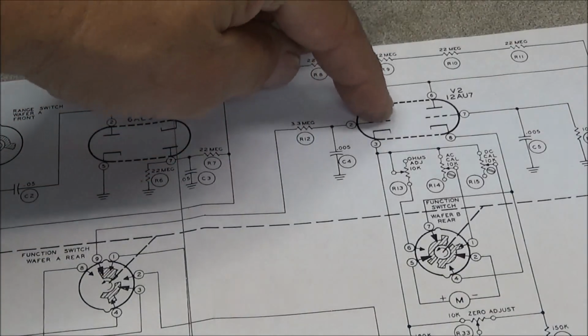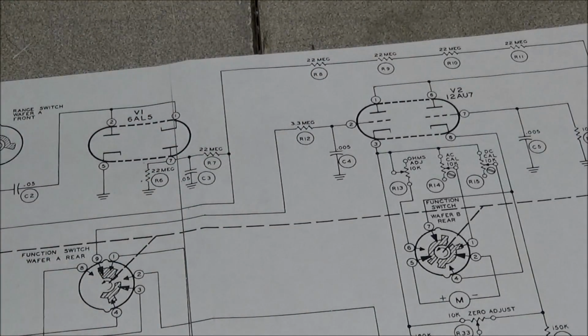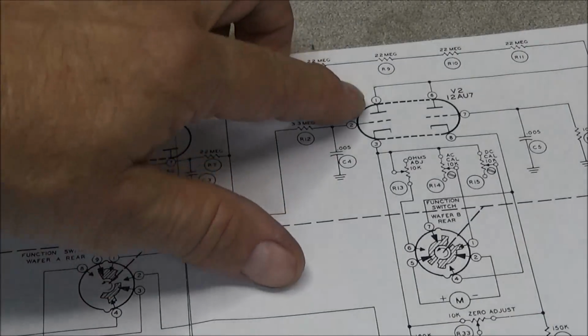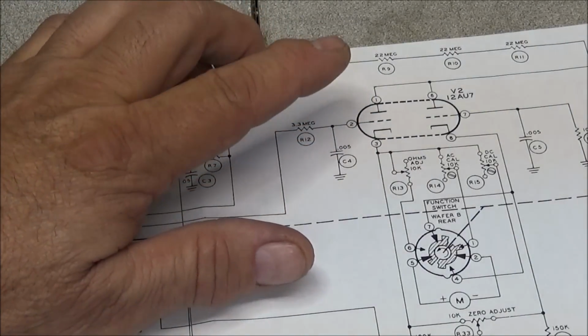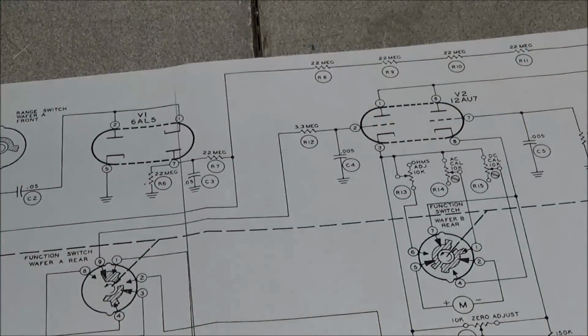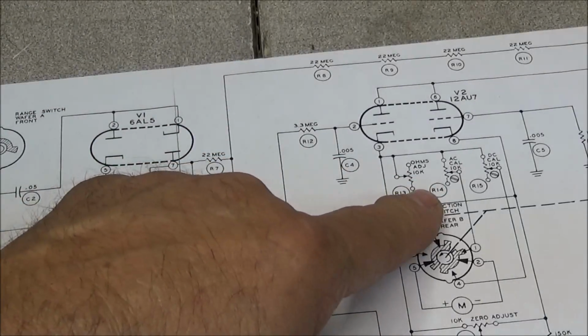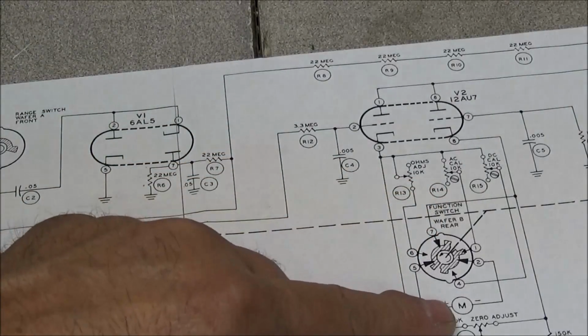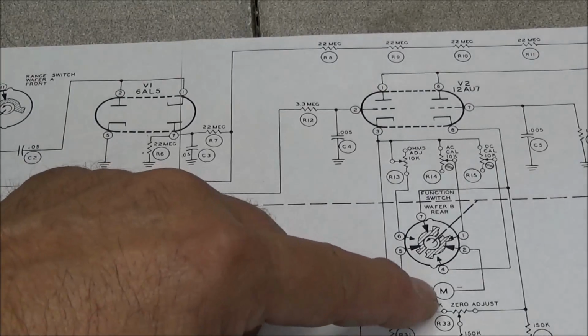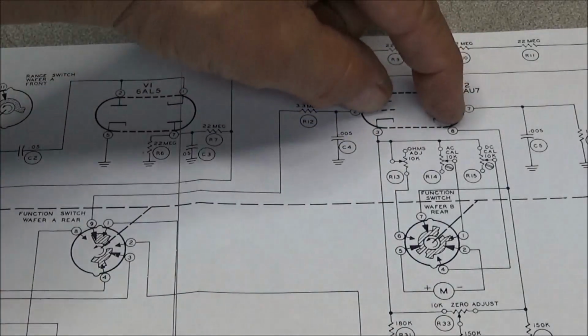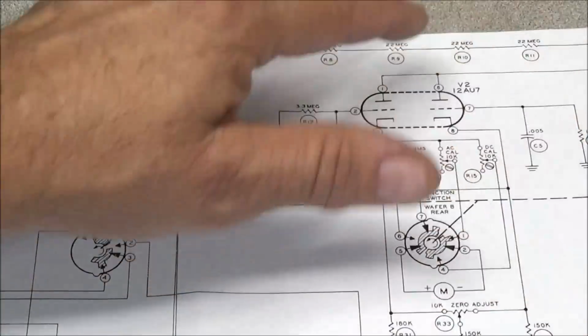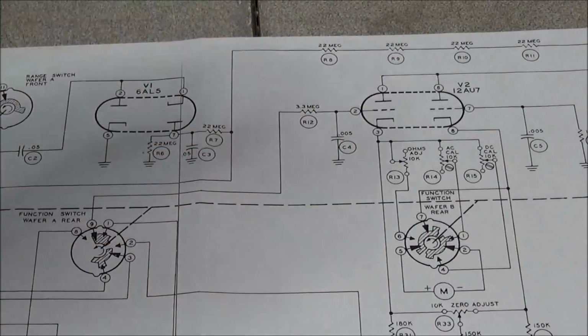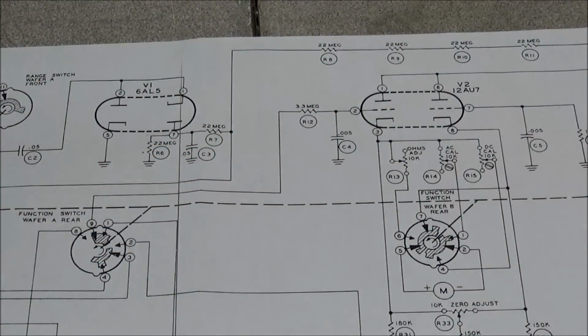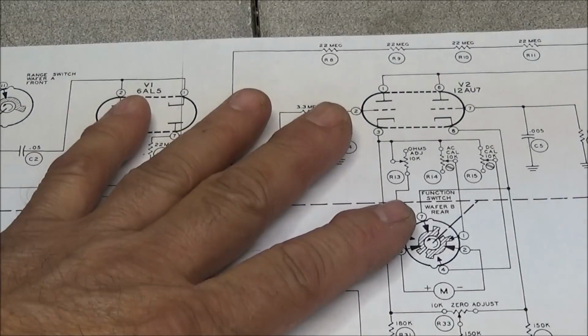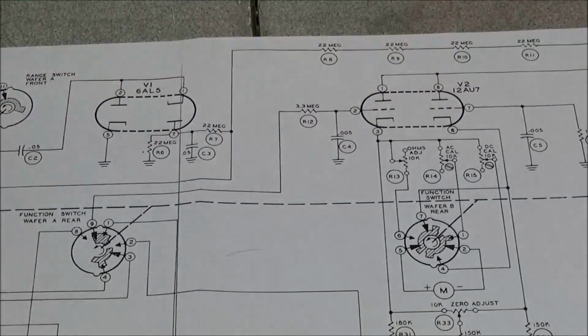And as it receives it, the voltage is picked off, and it causes one side of the tube to draw current, and that's what deflects the meter. If you see right here, the meter is actually in the middle of the two cathodes. So one side is fixed, the other side goes to the probe, and that causes the meter to deflect the correct voltage or meter reading.